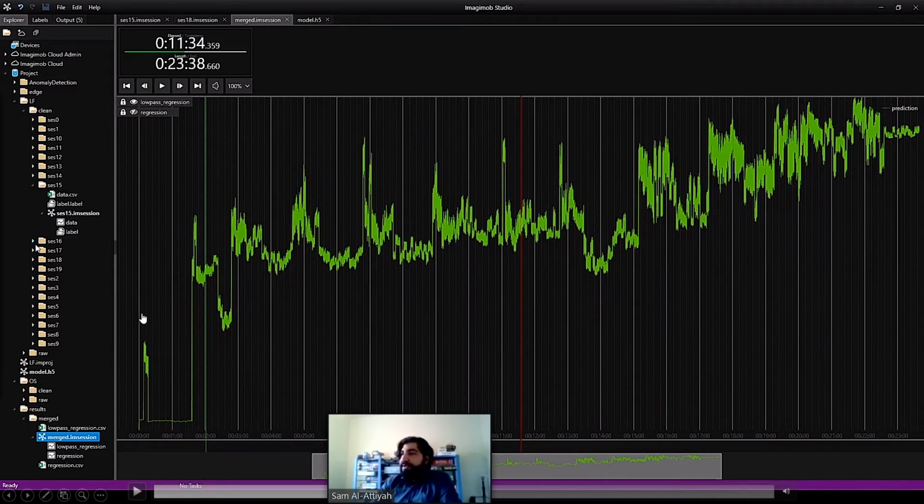But yeah, regardless of all these points, you can clearly see a trend going from healthy condition all the way to degraded condition. And at this last point, that's actually when the machine breaks down. So you have a breakdown in the winding, and then the machine is no longer able to run.